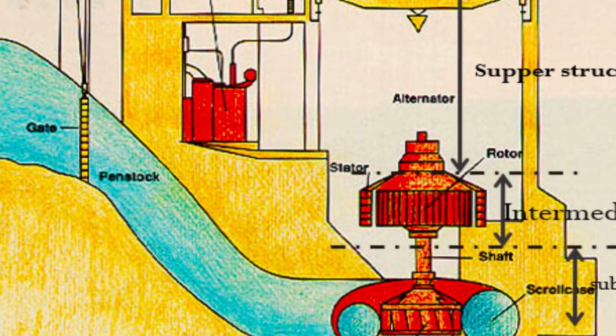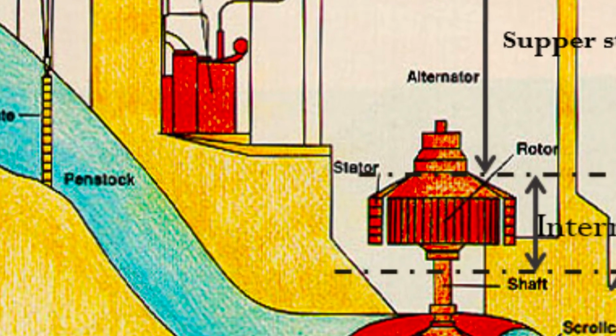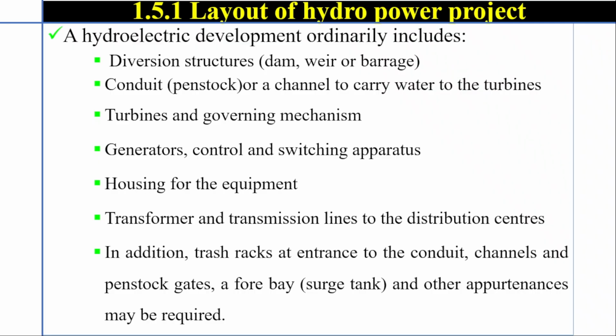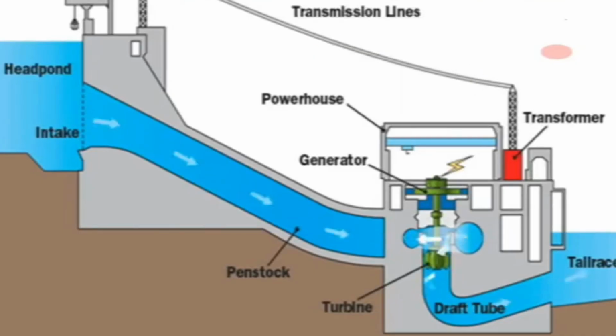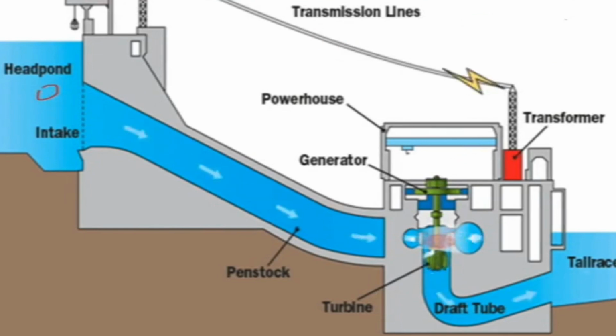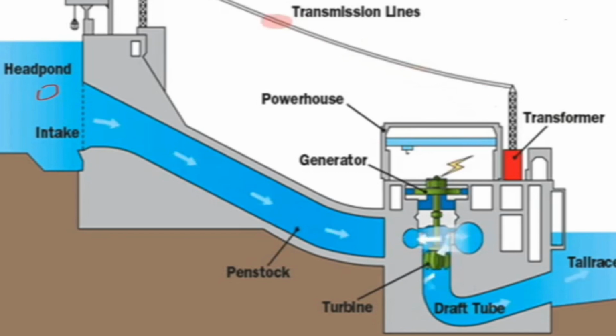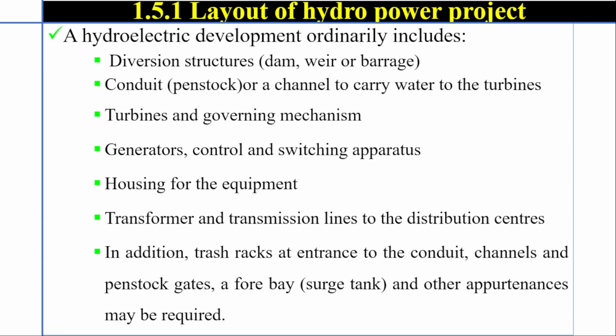Layout of hydropower project. The hydroelectric development ordinarily includes diversion structures or dam, weir or barrage, conduit or penstock or a channel to carry water to the turbines, and a governing mechanism, generators, control, and switching apparatus, housing for the equipment, transformers and the transmission lines to the distribution centers. In addition, trash racks at entrance to the conduits, channels, and the penstock gates, a forebay or surge tank, and other appurtenances may be required.